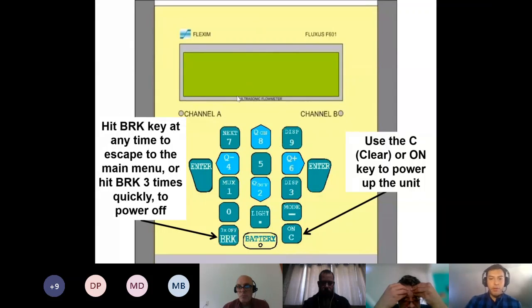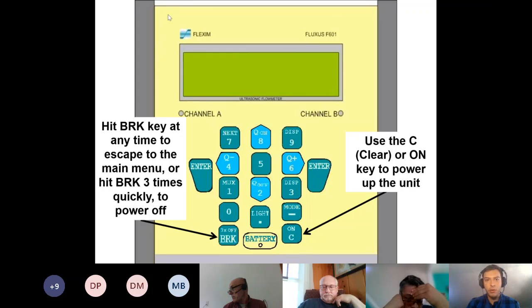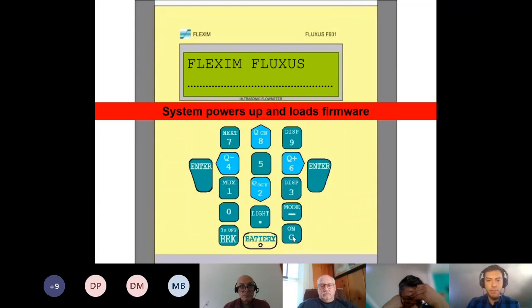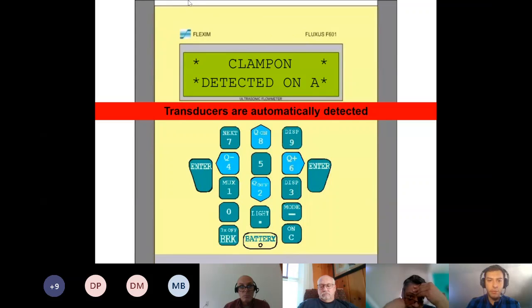So this should look very familiar to everyone with the portable version. This is the portable Flexim. As you know, it has two channels, A and B. A is in the top left, B is in the top right, and to get started, all you would have to do is plug your transducers into the appropriate channel. So plug your transducers and start with channel A and turn the meter on. When you turn it on, it powers up and you'll see all the calibration information be loaded right onto the Flexim.